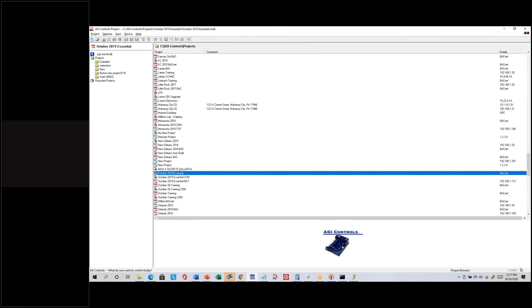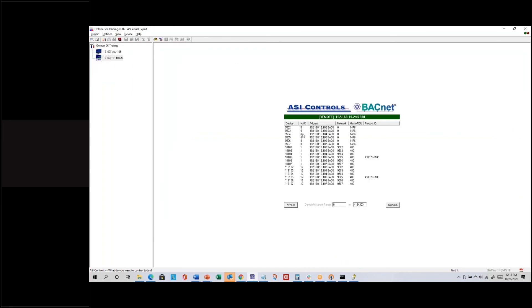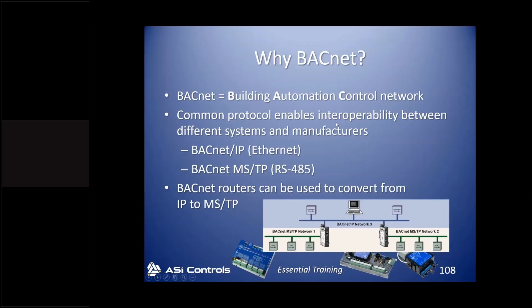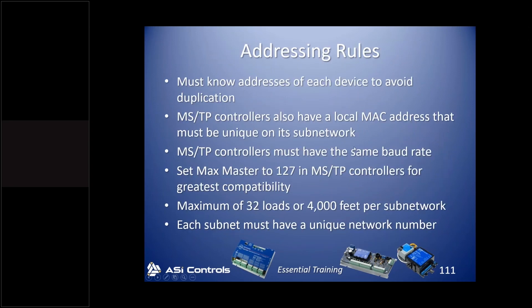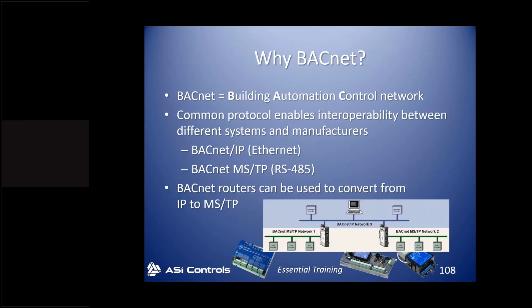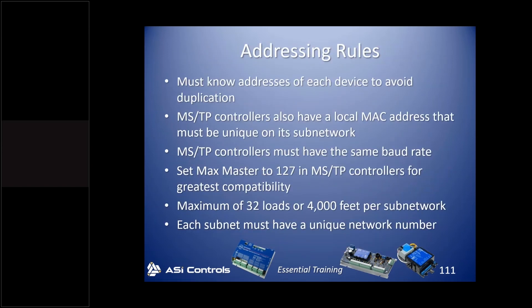Likewise, all VAV controllers can share the same MAC address because they're on different MSTP networks. Every controller on the same MSTP network needs the same baud rate — for example, MSTP Network 1 might all run at 38.4K while Network 2 runs at 76.8K; that's fine since they're different networks. There's also a Max Master setting usually left at 127. For absolute optimum communication, you'd want MAC addresses sequential starting from zero, with Max Master set to the highest MAC address on the network — but in the real world, defaulting to 127 is common to make adding controllers easier.